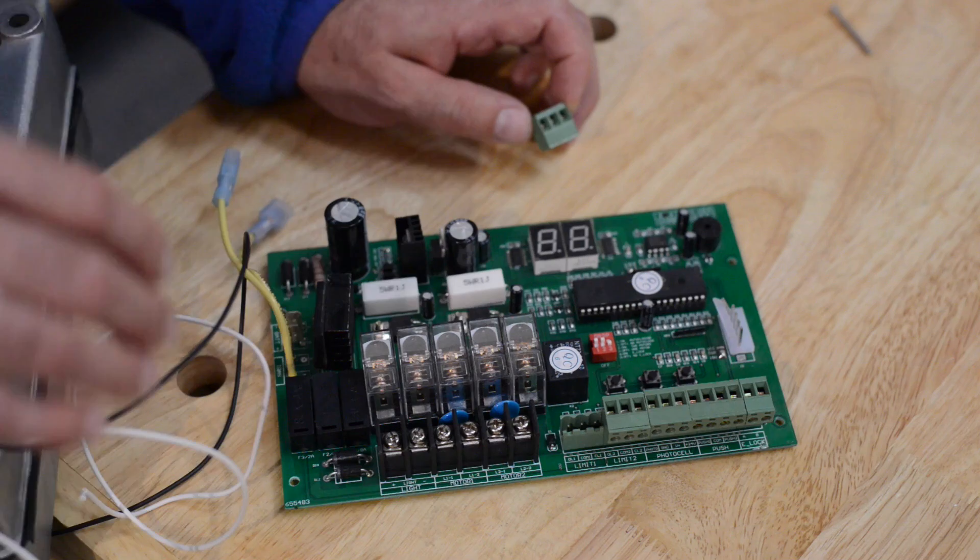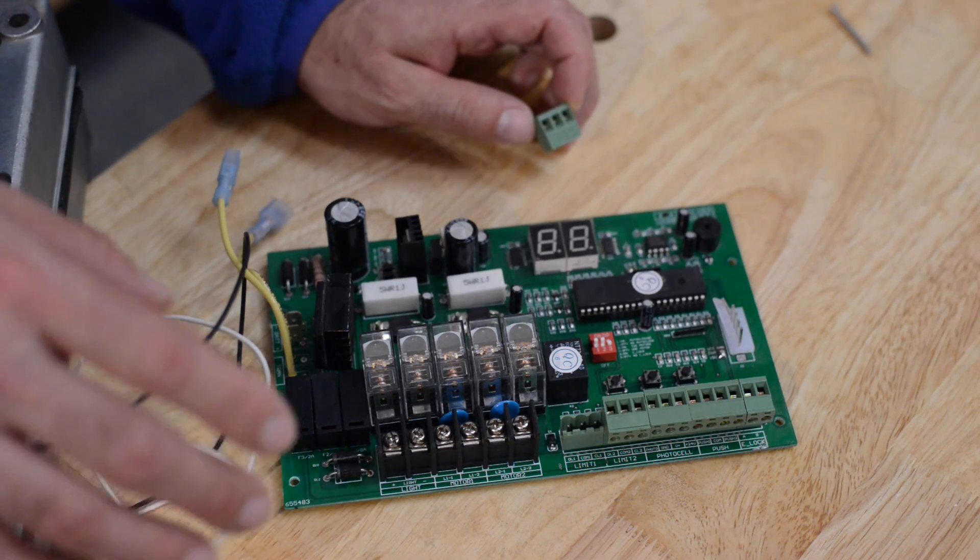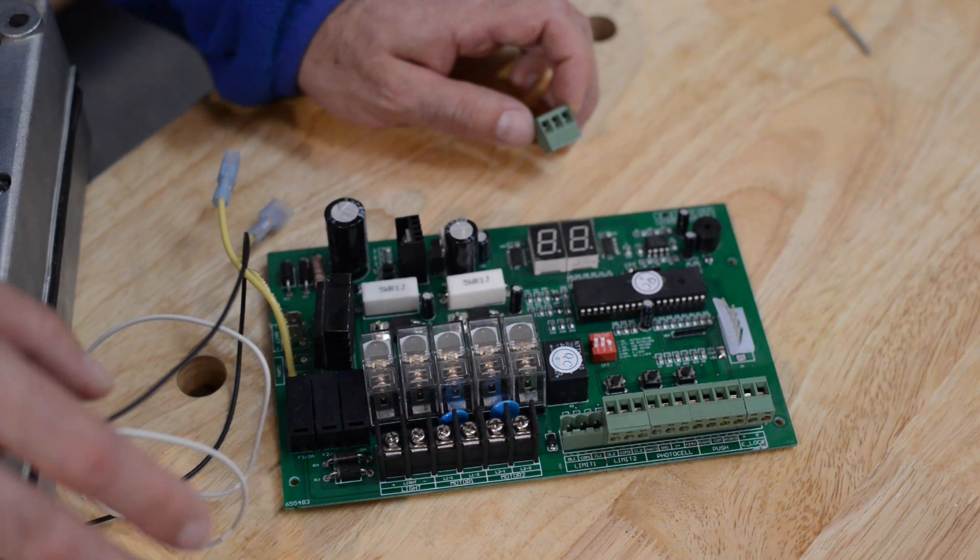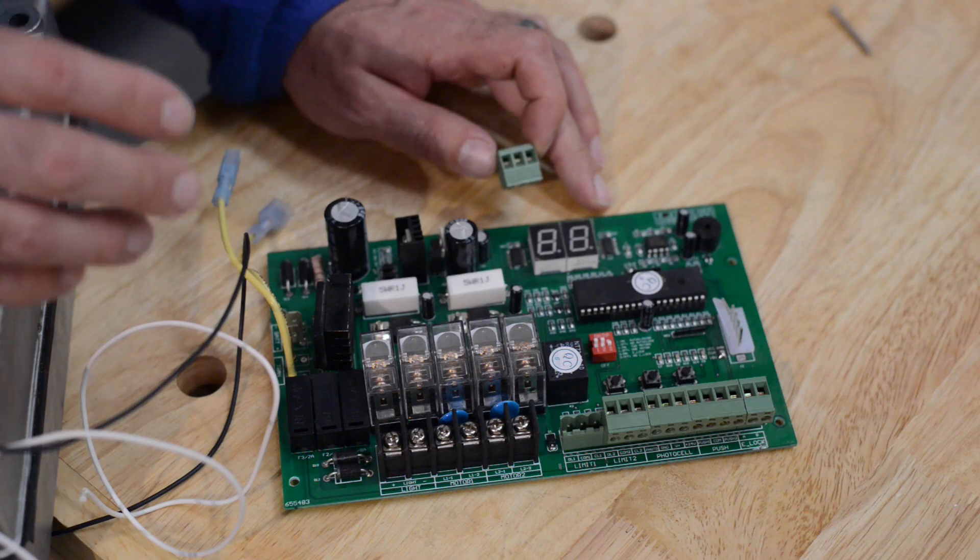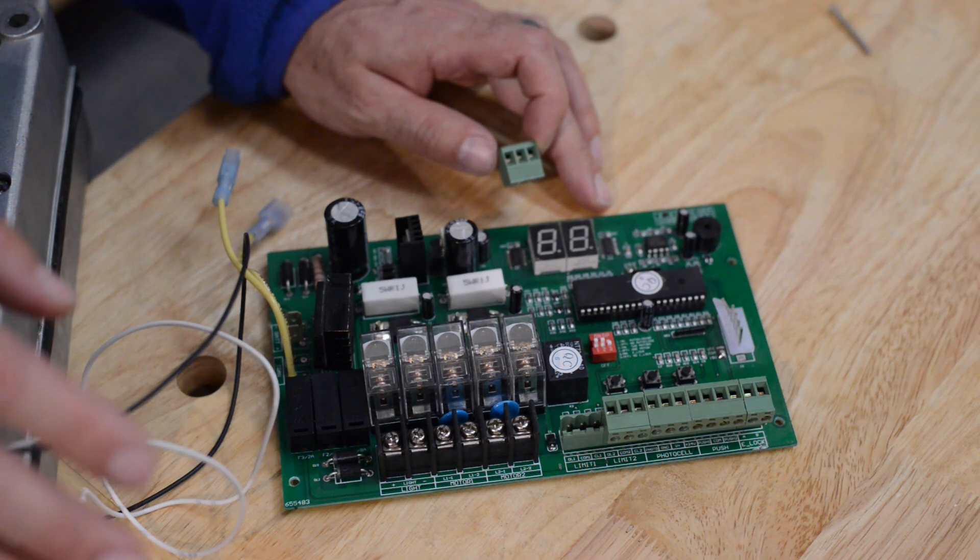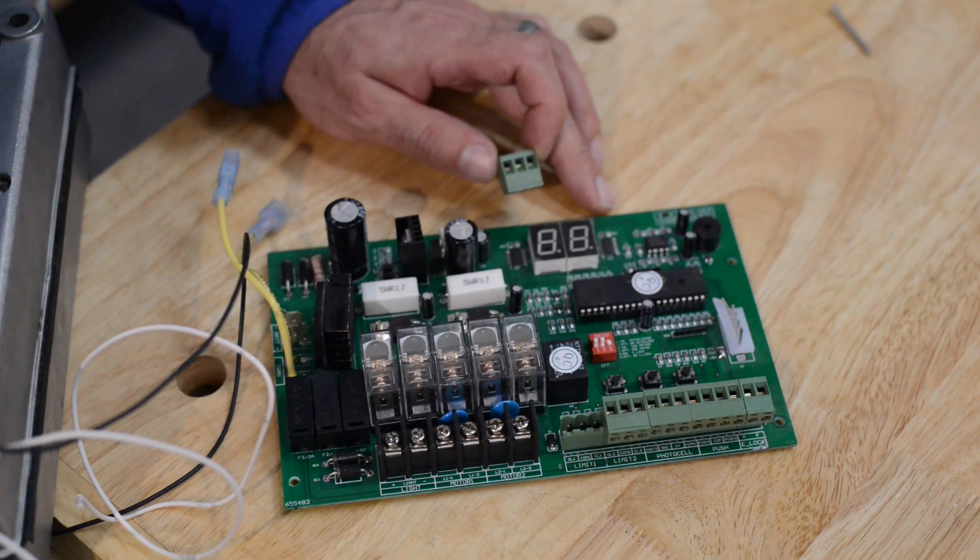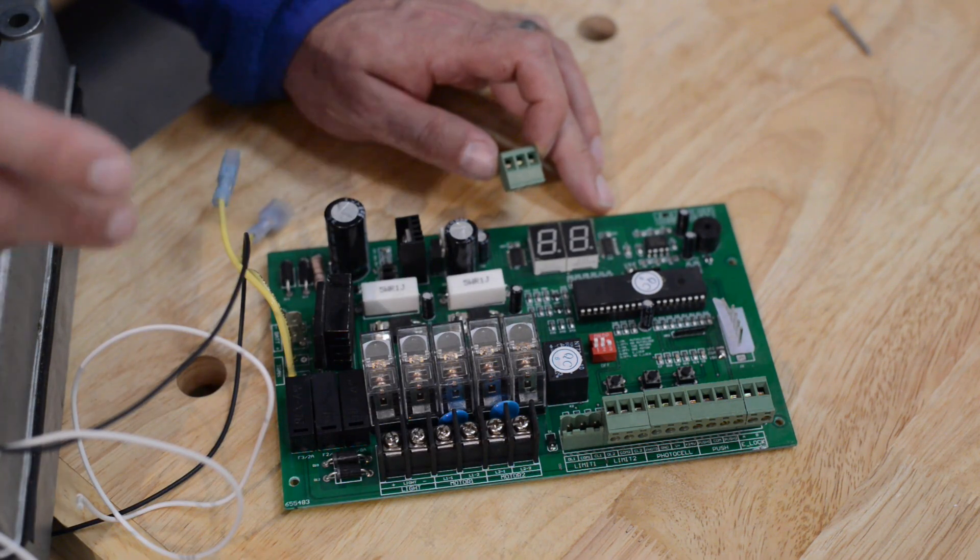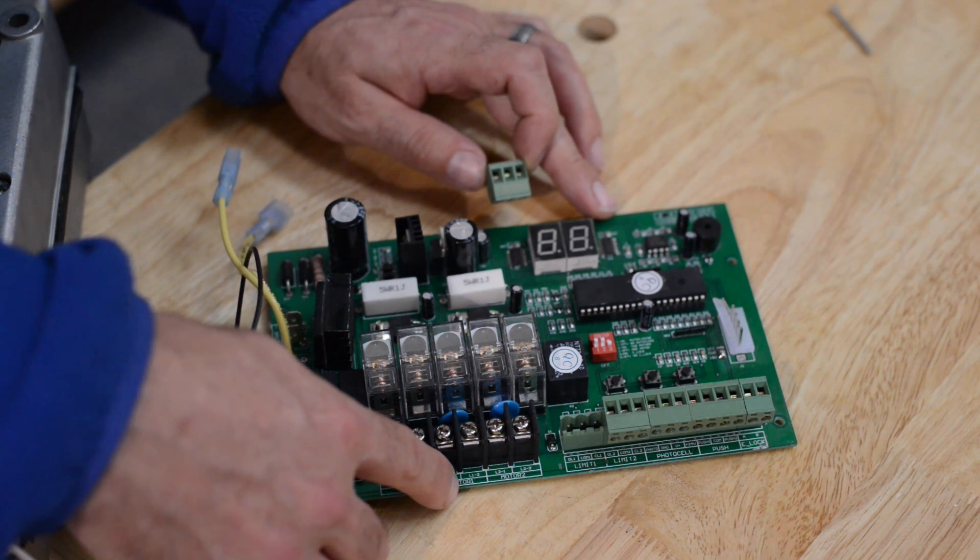Then from your open limit switch which you identified earlier out on the operator arm. You are going to take the wire that leads from the normally closed on the open limit switch and go to OL1. Then from the closed limit switch you are going to take the normally closed wire from the closed limit switch and bring it back to CL1. Then of course the two motor leads from that operator you want to go to motor one.